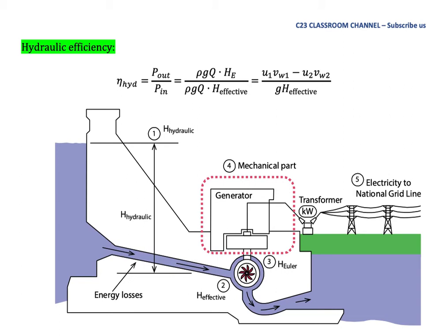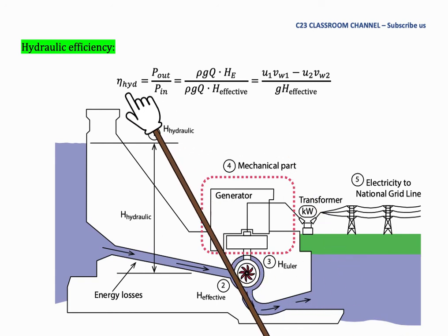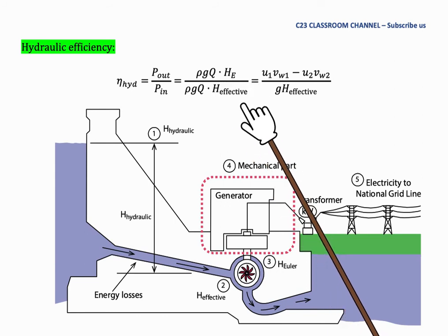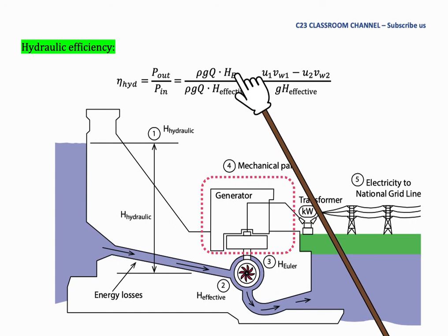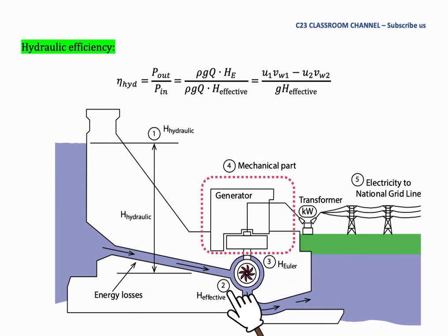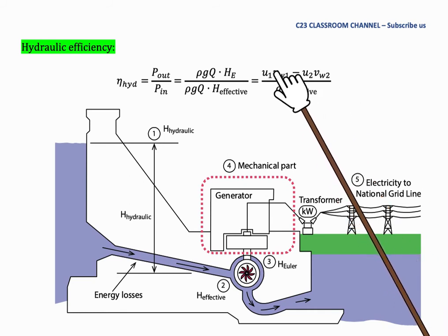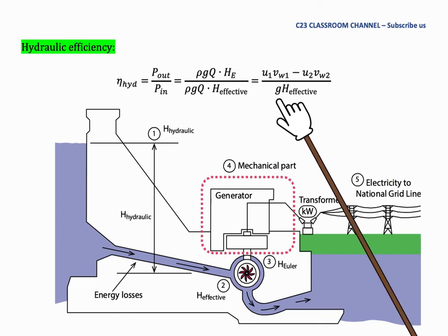Hydraulic efficiency can be defined as power out divided by power in. From this diagram, the power input for this Francis turbine is H_effective, and the power output is the Euler head. So we could write hydraulic efficiency as ρGQ·H_Euler over ρGQ·H_effective. If energy losses can be neglected, we could take the hydraulic head as the power input. Hydraulic efficiency can also be written as (U1·Vw1 - U2·Vw2) / (g·H_effective).